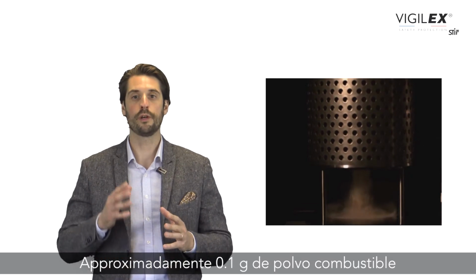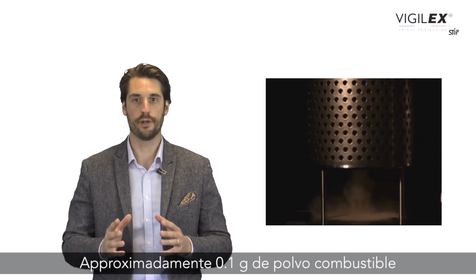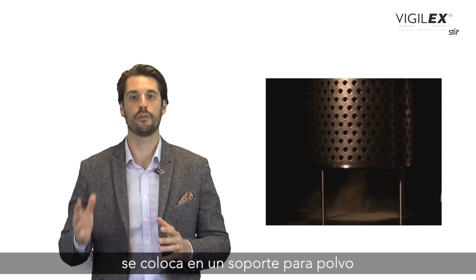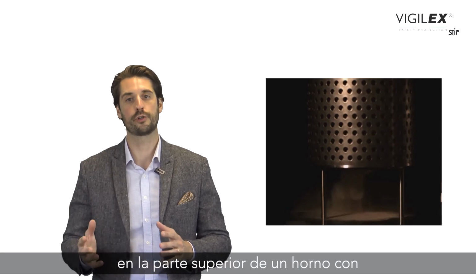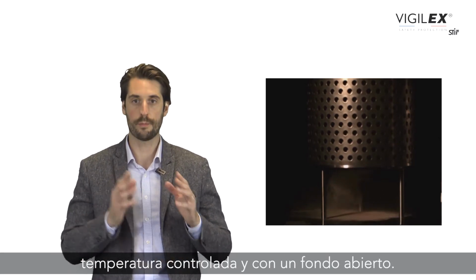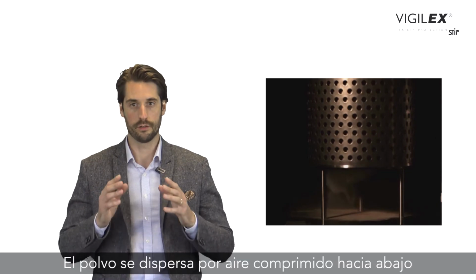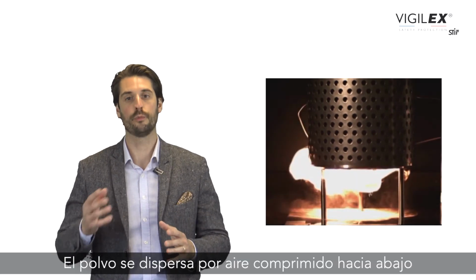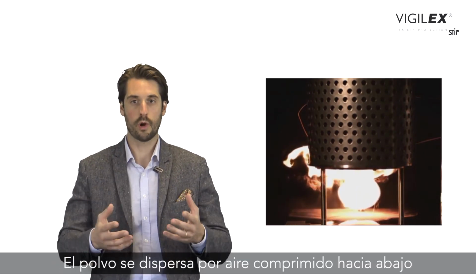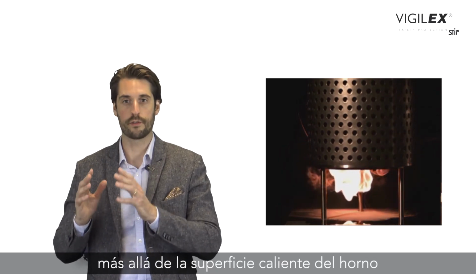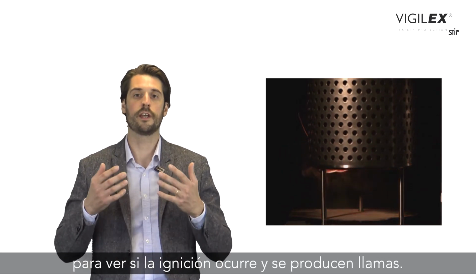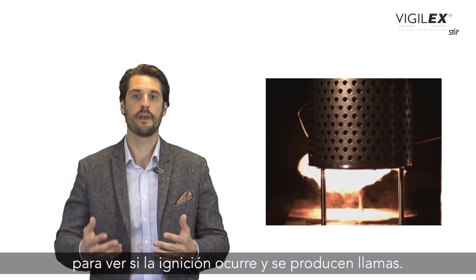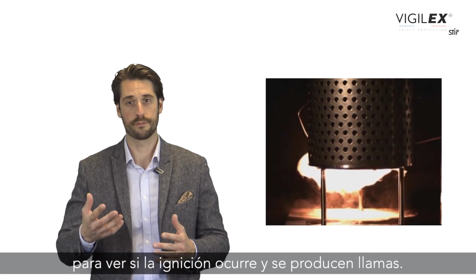Approximately 0.1 gram of combustible dust is placed in a dust holder at the top of a temperature-controlled furnace with an open bottom. The dust is dispersed by compressed air downwards past the hot surface of the furnace to see if ignition occurs and flames are produced.